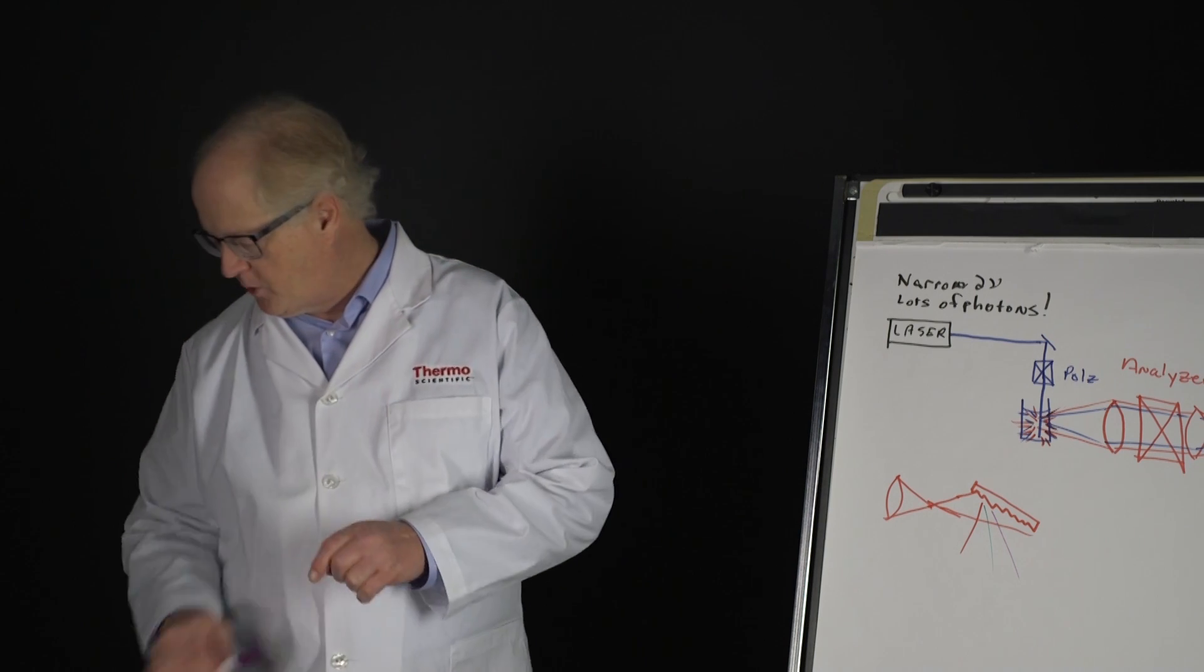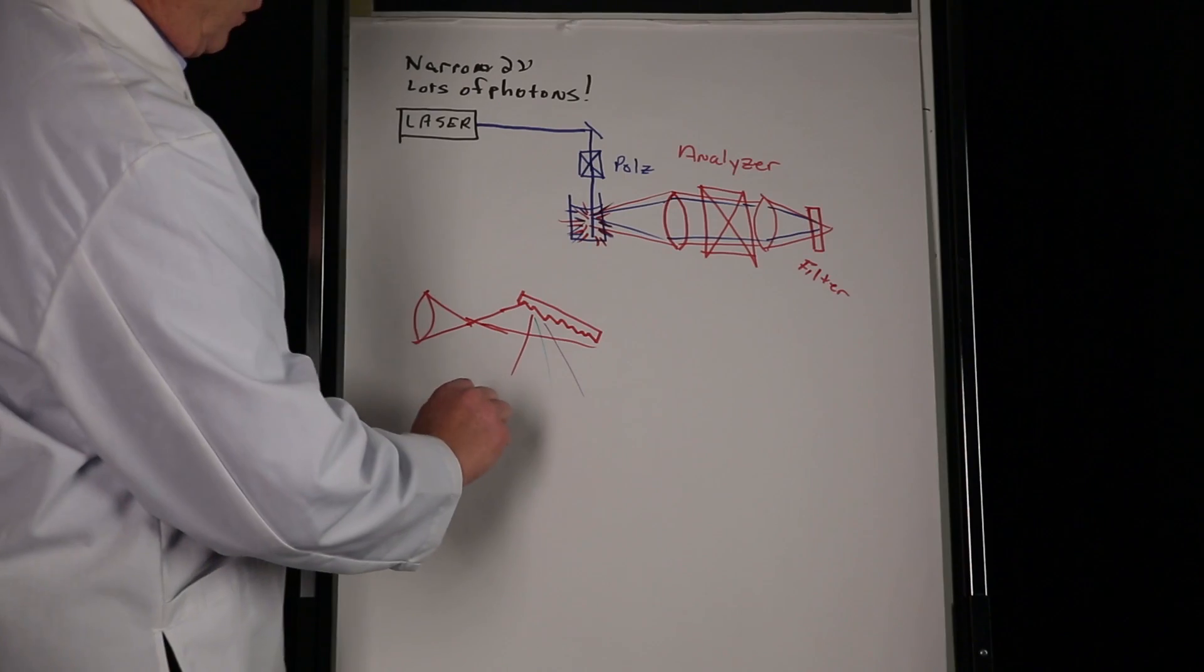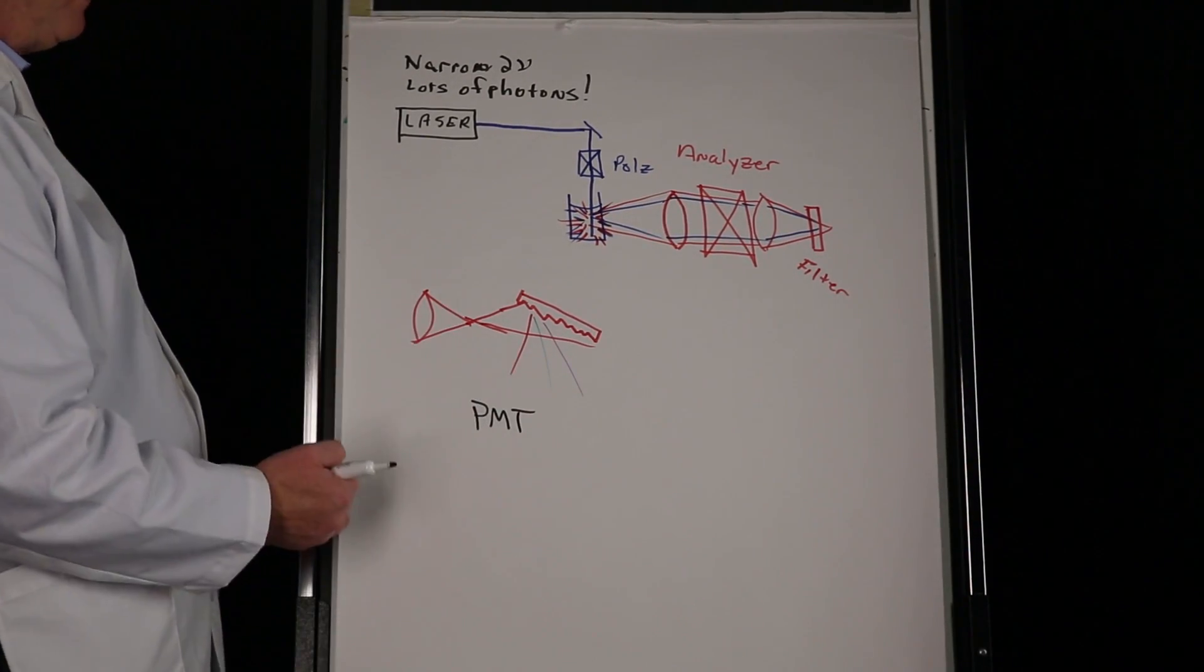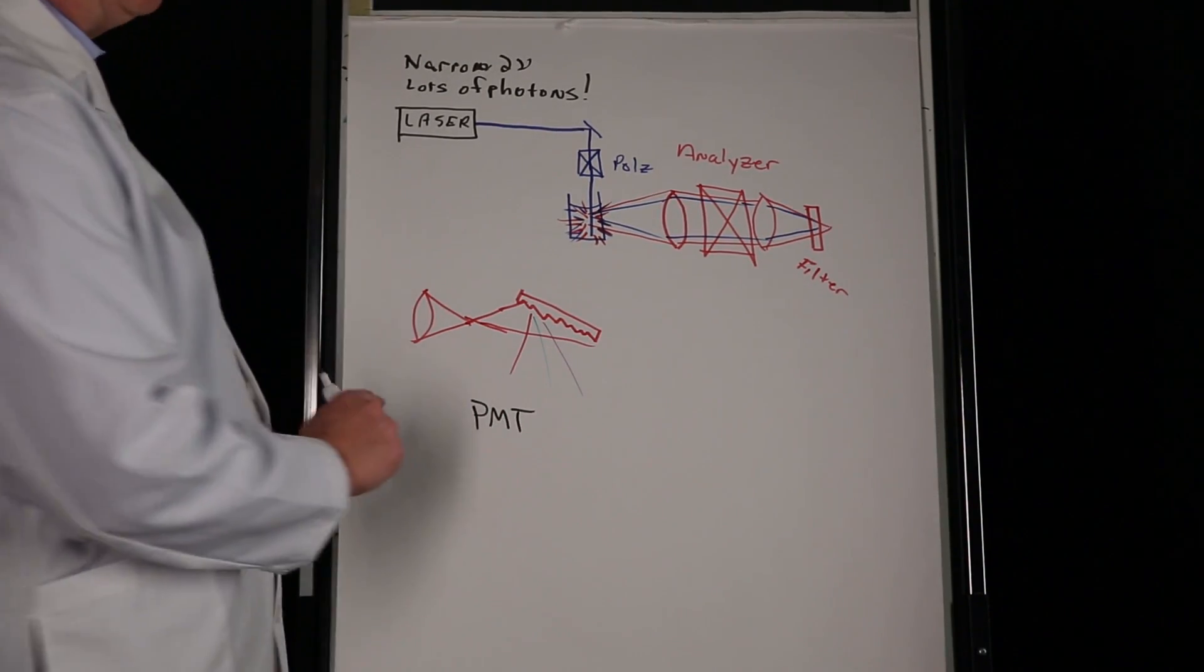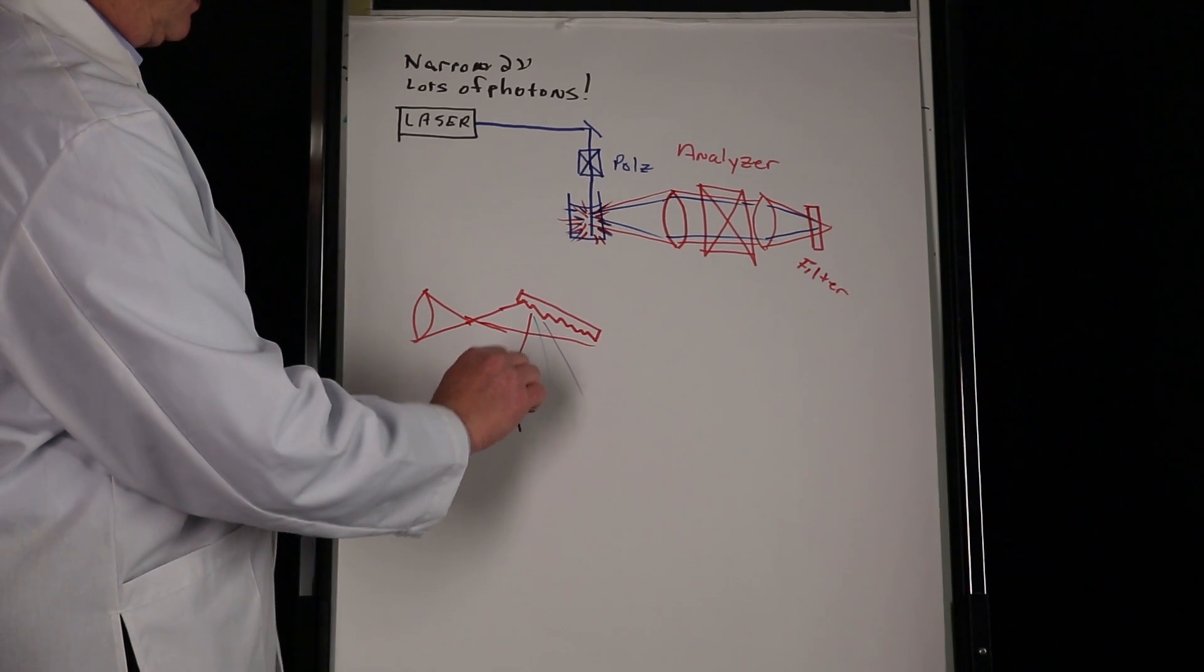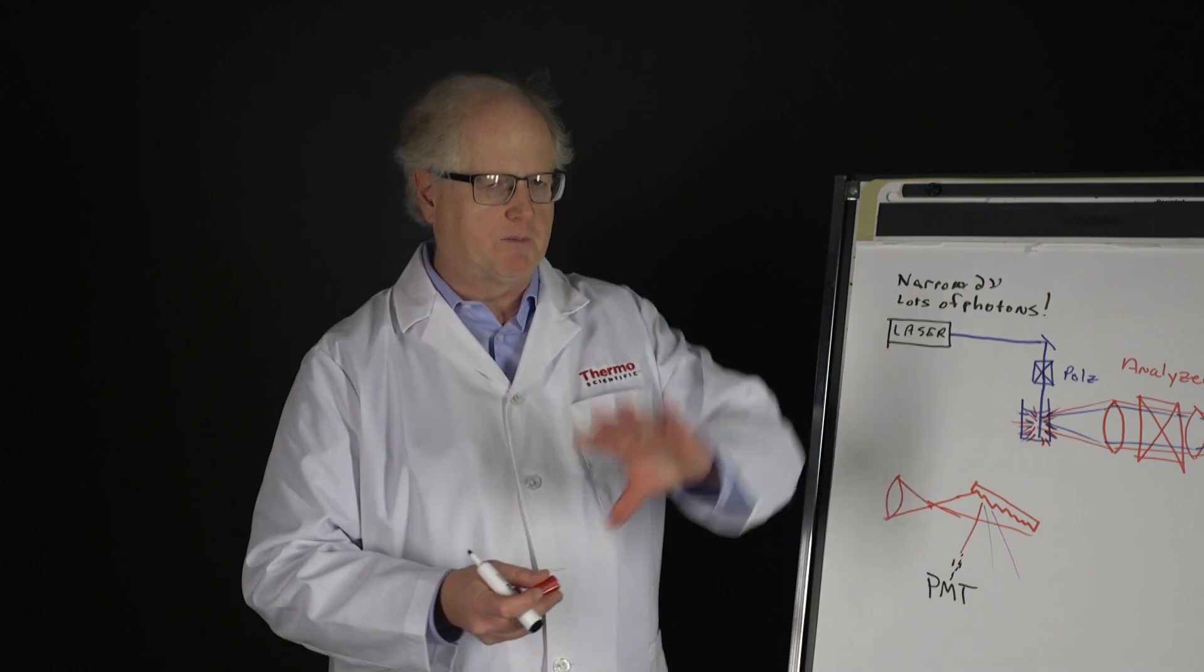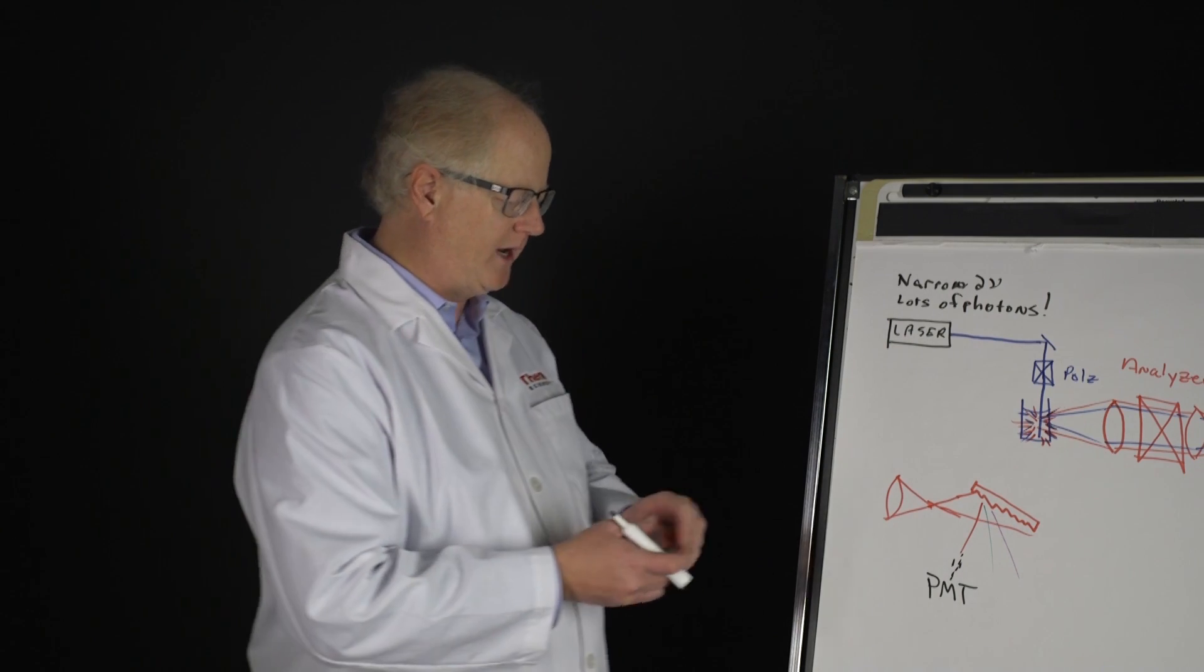Now in a classic Raman spectrometer, what I would then have is a photomultiplier tube, PMT, which we'll describe a little bit about how that works in the next video. That PMT, however, is a single point detector. So you would have a slit, a narrow slit. The light would travel through that slit, hit the PMT. And then in order to take the spectrum, you would have to rotate the grating. You'd have to rock that grating around.